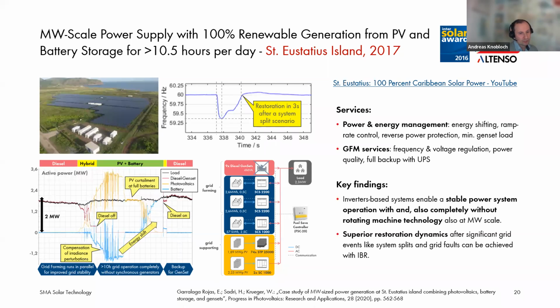Our key findings in this project were that inverter-based systems enable stable power system operation with and also completely without rotating machine technology, also at megawatt scale. This is very important because there are many people outside who do not believe that it is possible, but it is. Another important finding, as we see here on top, is that inverter-based systems, or grid-forming systems at least, allow superior restoration dynamics after significant grid events like system splits and also grid faults. Dynamic processes that take minutes in the public power systems with conventional equipment and its inertia can be accelerated by inverter-based systems by far. So you see here a restoration within 3 seconds compared to maybe 1, 2, 3 or 5 minutes in the public power grids.